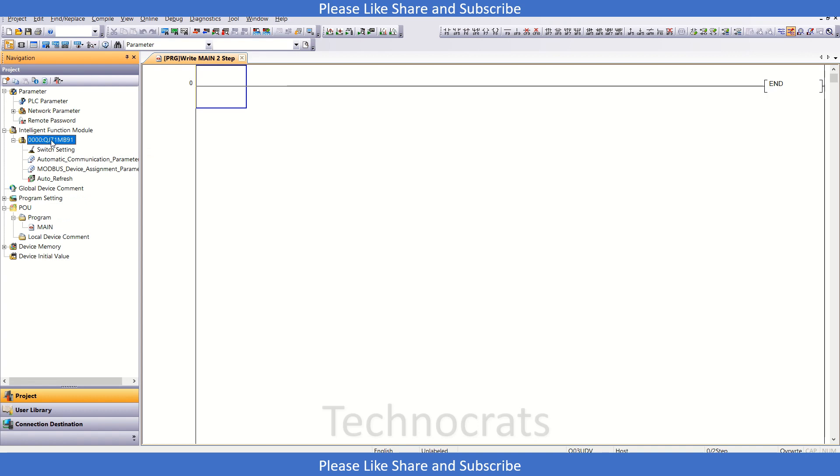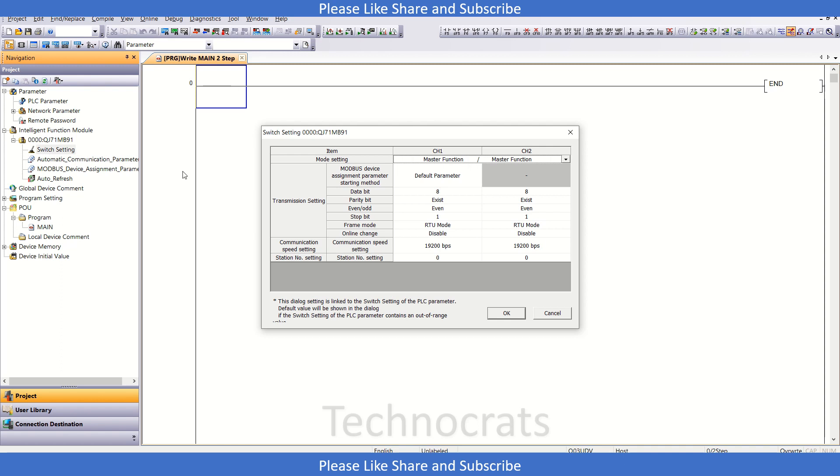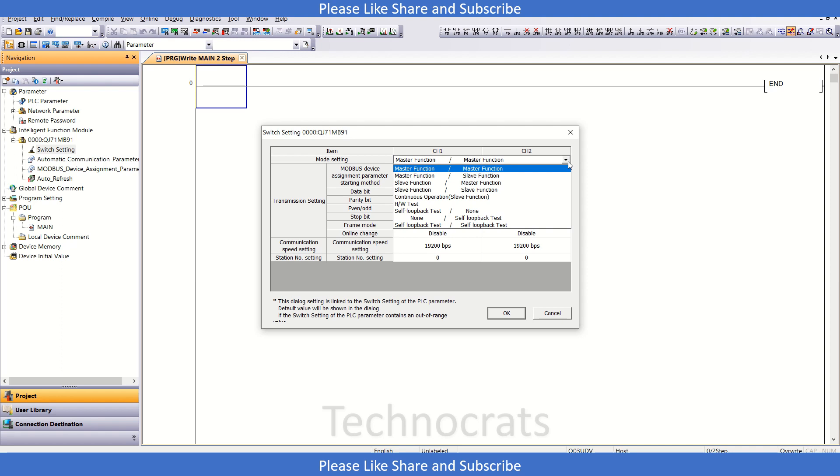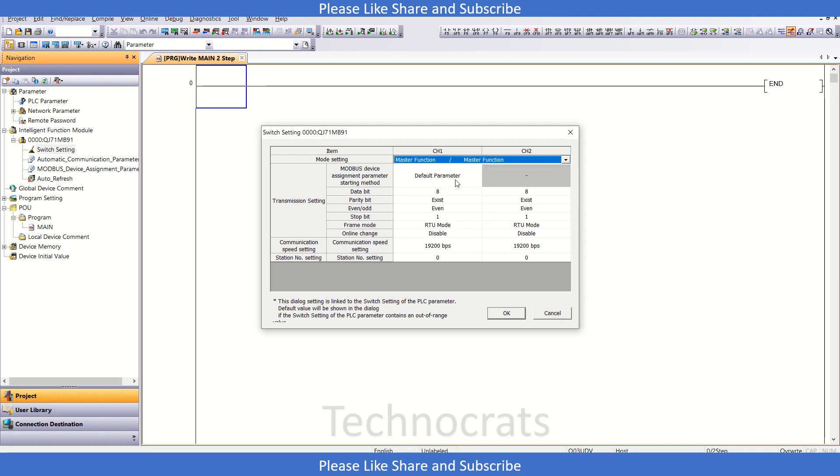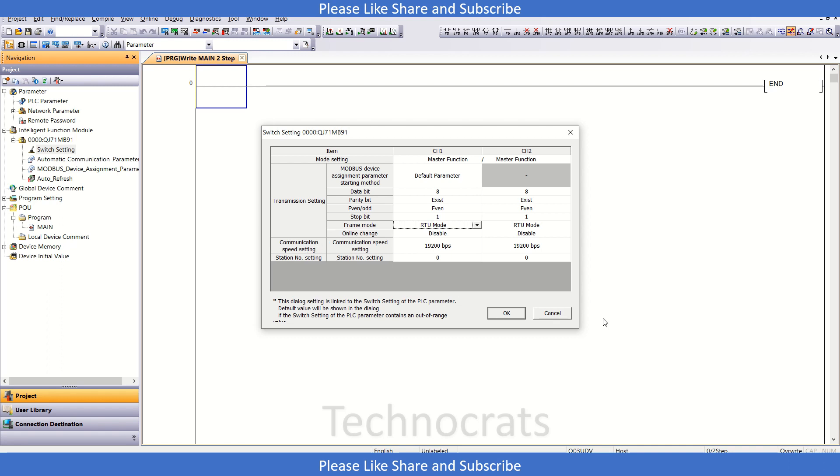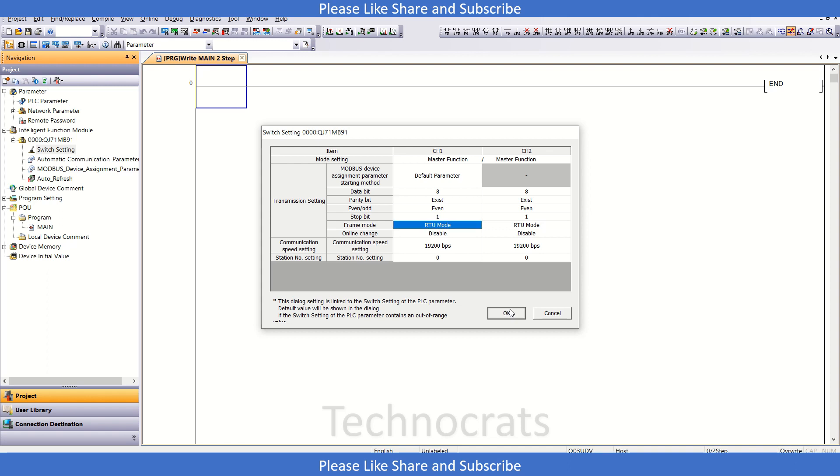Now what I have to do is use the settings here. I'll go to the switch setting, and we have this master function selected. The data bit is 8, parity exists and is even, the stop bit is 1, frame is RTU mode, and the speed is 19200 BPS. I will just click OK. If you want to change some of these settings, you can.